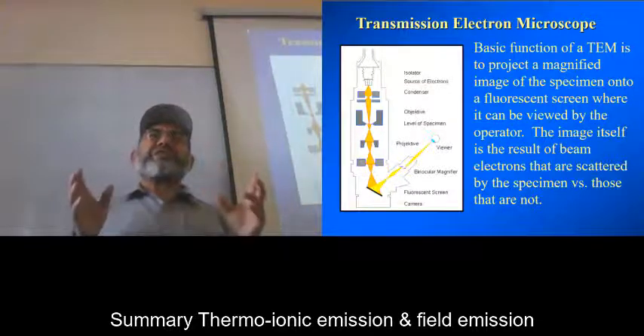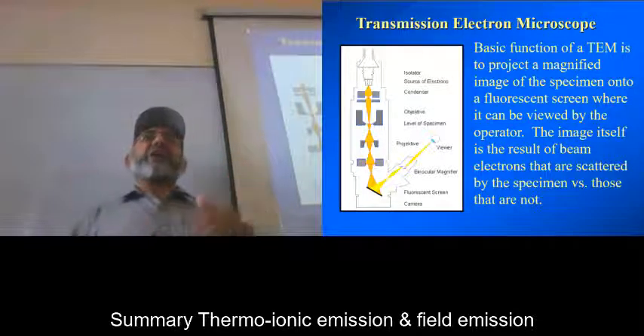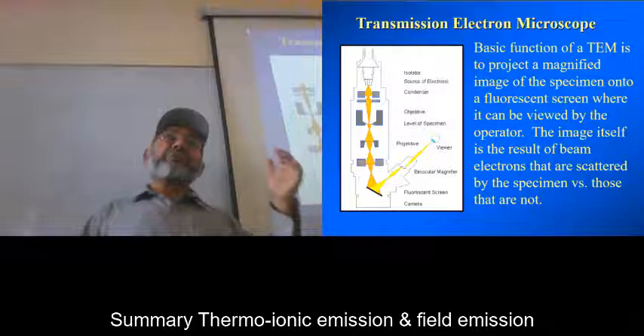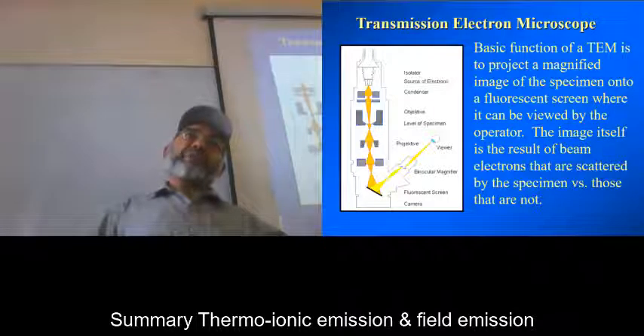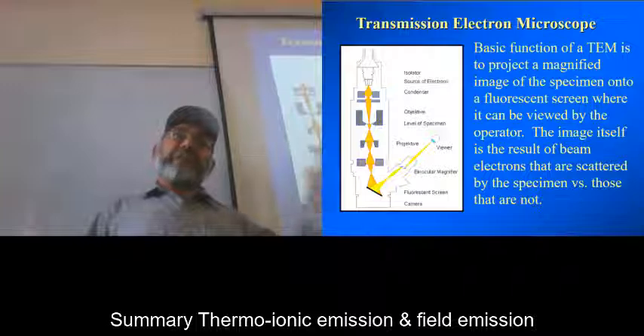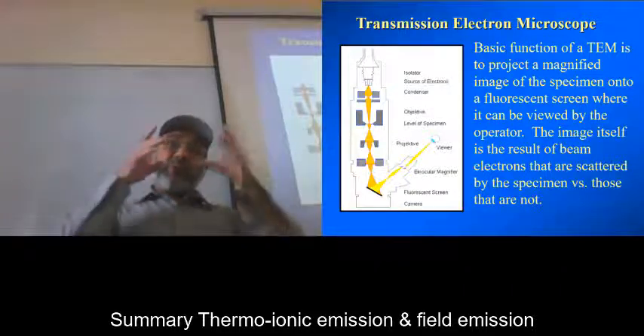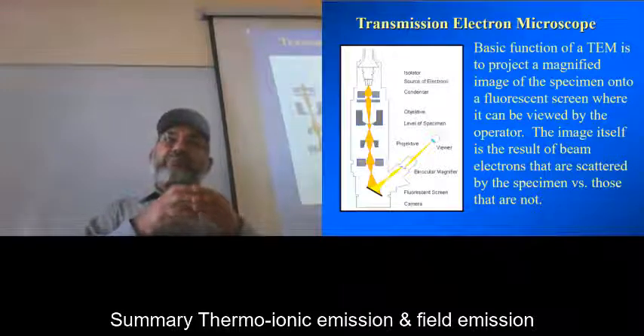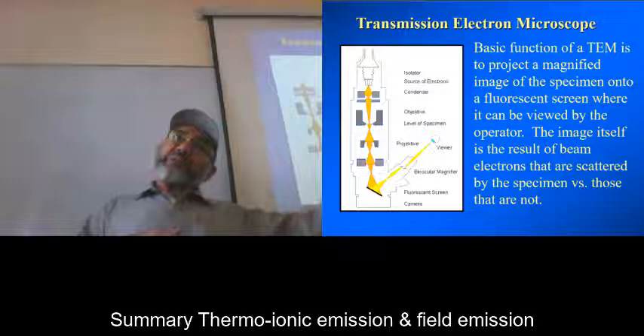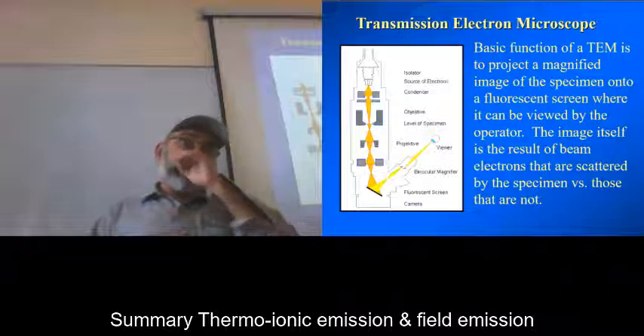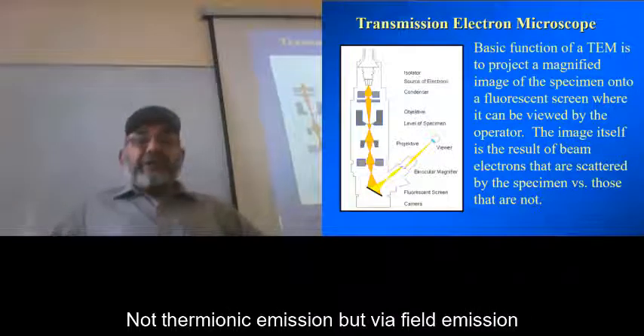But the most sophisticated machines are using field emission guns. Because field emission guns give you edge over the thermo-ionic emission in the form of the resolving power of the microscope, in the form of the very high magnification images. Because the more organized the beam is, the easier it will be to interpret the images, to make the images, to get the diffraction patterns and things like that, than with the thermo-ionic emission.